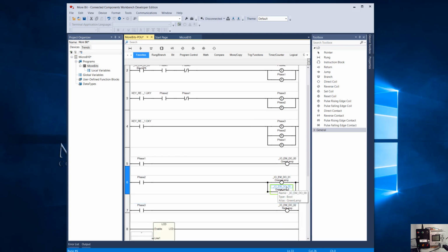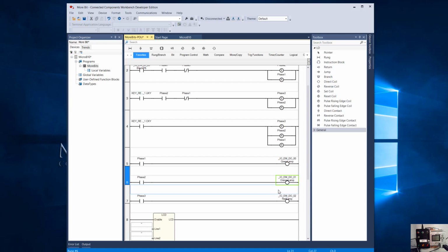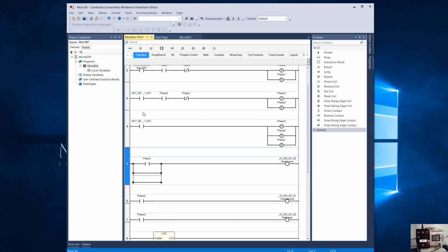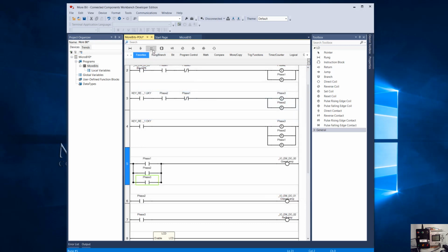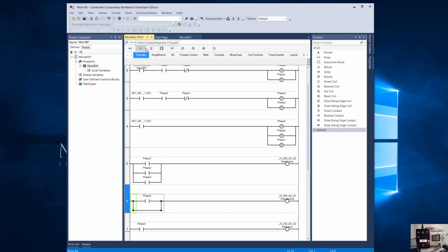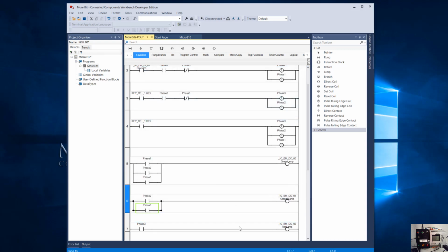So hopefully you can see that I can create the same function, having both the orange lamp and green lamp on, without addressing the green lamp twice. By, instead of doubling up on the output, I can double up on the input. So I say I want the green lamp on in all three phases. And I want the orange lamp on in phase 2 and in phase 3. And then the red lamp only comes on in phase 3. So you can see I'm still only addressing each of those outputs in one location, but they're going to be on in multiple phases. So let's just download that.